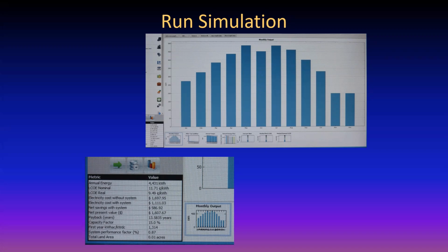One thing about any kind of fossil generator is that if you've got, let's say, a 5 kW fossil fuel generator and your load on it is only 200 watts, the efficiency is really, really small. You're making electricity at something like $1 to $1.50 per kilowatt hour doing that, so you really don't want to do that. If you have a gasoline generator, you would like to run it at 80 to 90% of its rated output. And if you have batteries to store that output in, then you don't need to run it nearly as long. The batteries make the system a whole lot more efficient, and you don't have to breathe that smelly diesel fuel, or even natural gas, which gets pretty smelly if you have a really big generator. All right, so that's my comment on that.